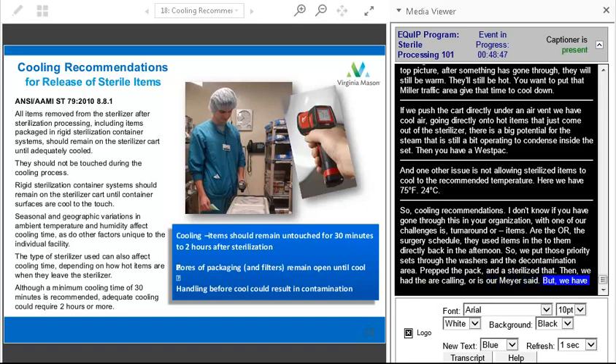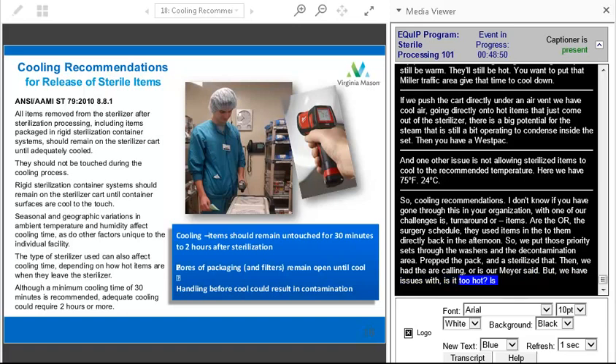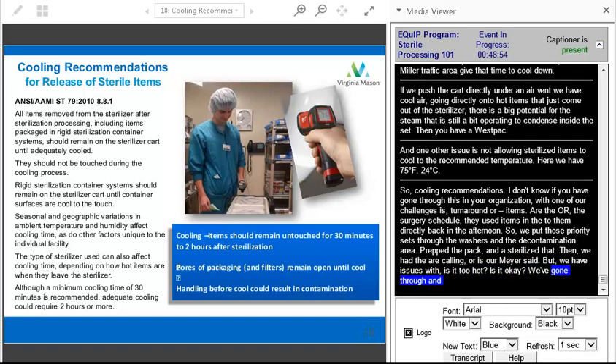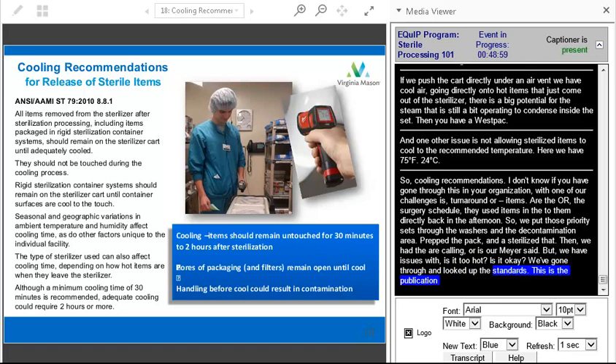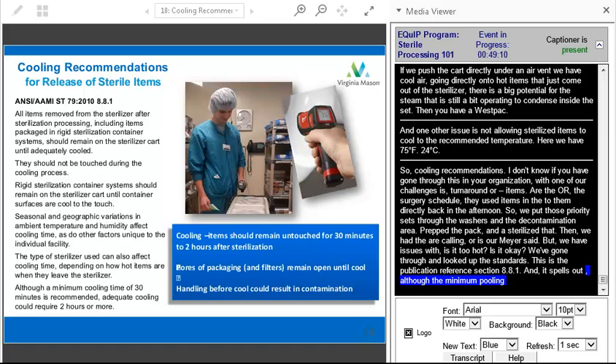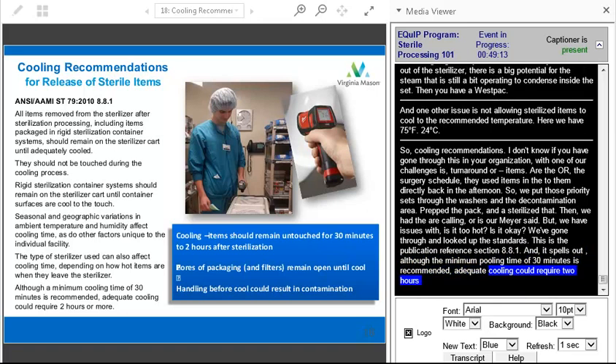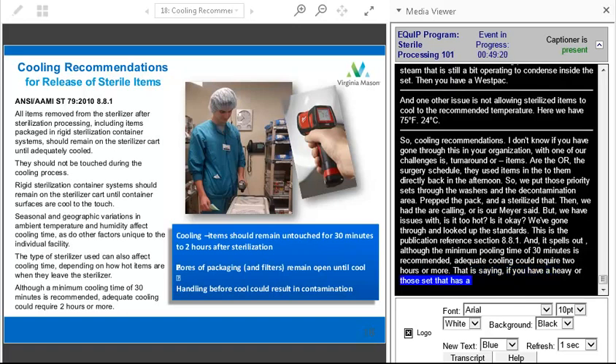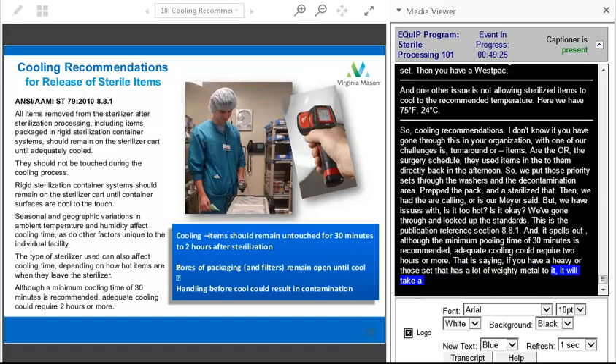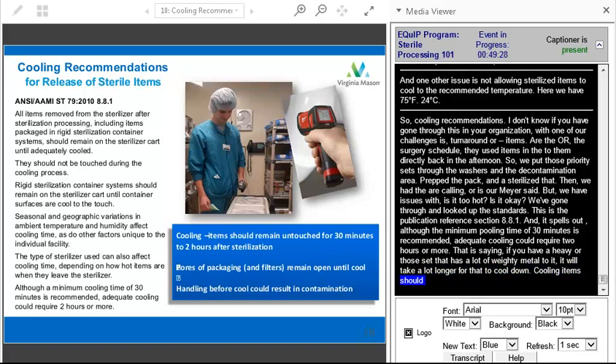Is it okay? So we've gone through and looked up the AAMI standard and the ST79. And so this is the publication reference, section 8.8.1. And it spells out here, although the minimum cooling time of 30 minutes is recommended, adequate cooling could require 2 hours or more. And that is saying, if you have a really heavy, say, ortho set that's got a lot of weighty metal to it, it's going to take a lot longer for that to cool down. So cooling items should remain untouched for 30 minutes, up to 2 hours after sterilization.